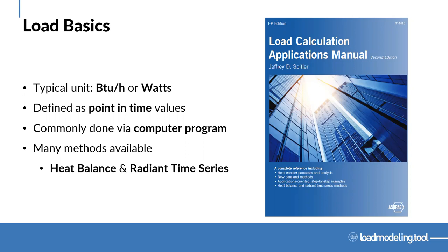Typically these are going to be done with a computer program. There are means to do it by hand — we had to calculate loads far before computers — but I certainly wouldn't recommend that today. It will be time consuming and very difficult to do at scale. There are many methods available: heat balance and radiant time series are by far the top two, but there are nuances. You can see these in many calculation programs and in ASHRAE Fundamentals. They'll discuss the various differences, but they're all essentially going to get you to a similar answer of how much heat's in my space and what do I need to deliver to counteract that.